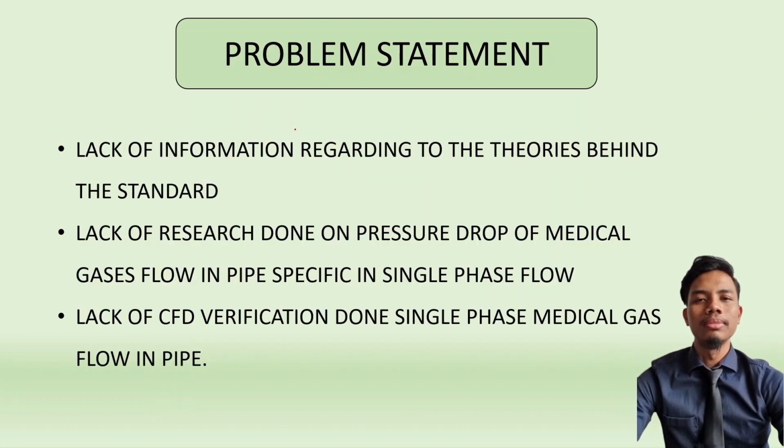Next, problem statement. As we know, piping system design requires a standard. Various standards propose different design requirements. Since the HTM standard is a relevant standard used as a reference in designing piping systems, and there is a lack of information regarding the theories behind the standard, it is needed to study the standard, specifically Appendix G from HTM 02-01, and verify the data with CFD analysis and theoretical data.